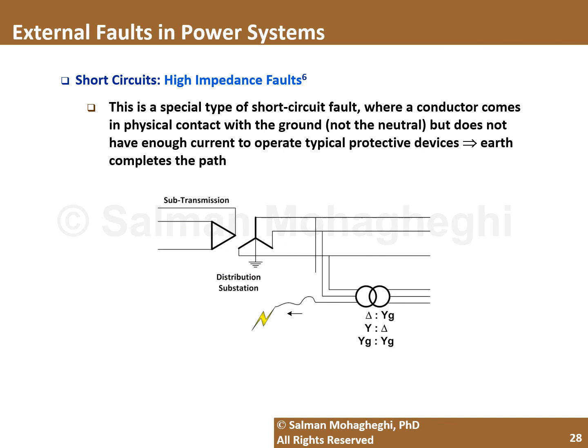Within short circuits, we also have high impedance faults. This is a situation where you have a short circuit, but the short circuit current is not high enough for the protective relays to pick it up and isolate the faulty circuit. This sometimes happens when you have, for example, a conductor that breaks and comes into contact with the ground. So some fault current will flow to ground, but this is small enough that none of the overcurrent protection devices would pick it up. So essentially, your earth is going to be completing the path of the current.